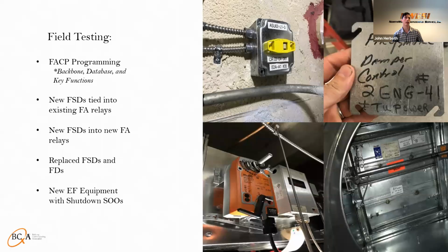Let's keep going. What you're going to end up finding that you really need to start learning in these areas at a hospital specifically, and once you get into other places like any high occupancy building, is that the fire damper relays that control and connect to the fire alarm system need to be inspected to make sure that they are labeled correctly and landed correctly. One of the problems that we ran into in this hospital was when we went to go testing. We did all this coordination to make sure that stuff shut down correctly and closed. And we found stuff didn't close or it didn't respond at all.